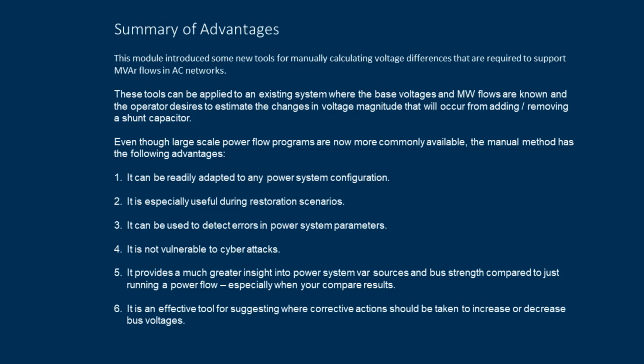They can be applied to an existing system where the base voltages and megawatt flows are known, and an operator desires to estimate the change in voltage magnitude that will occur from adding or removing a shunt capacitor. They can also be used to estimate the participation of other generators in the megavar flows when shunt capacitors are removed from or added to a network.